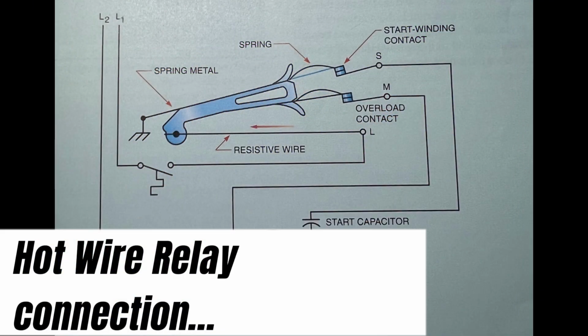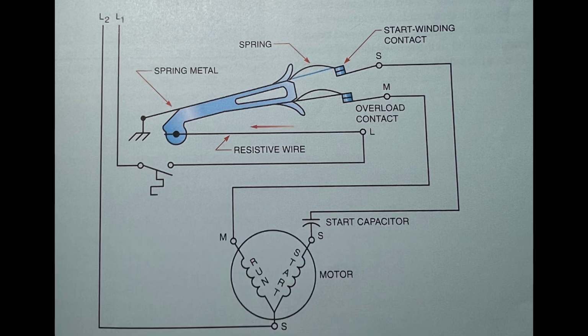Hot wire starting relay. Centrifugal switches cannot be used on all types of split-phase motors. Hermetically sealed motors used in refrigeration and air conditioning, or submerged pump motors, must use some other means to disconnect the start winding. Although the hot wire relay is seldom used anymore, it is found on some older units that are still in service. The hot wire relay functions as both a starting relay and an overload relay.